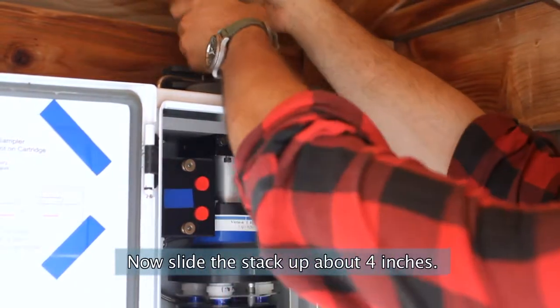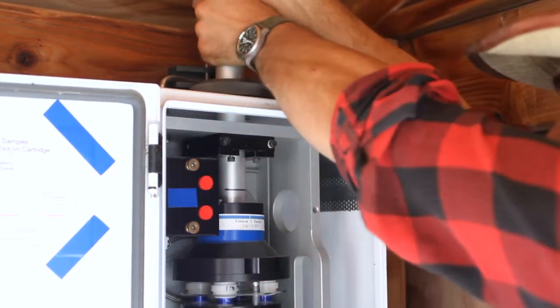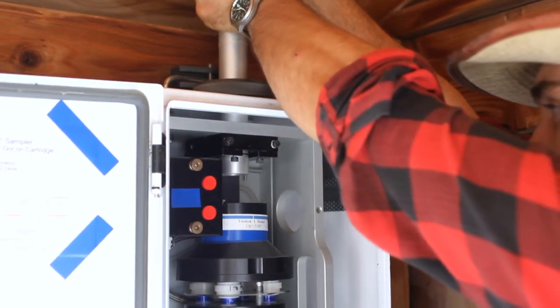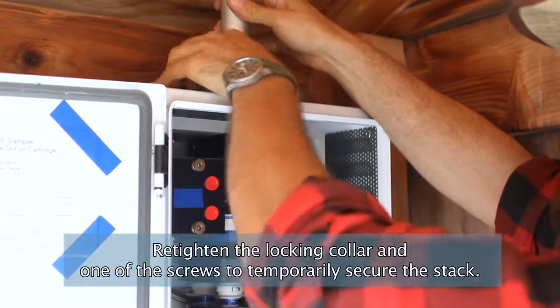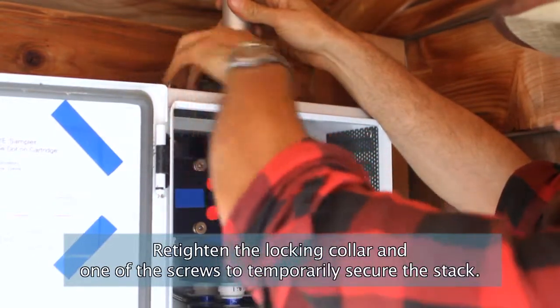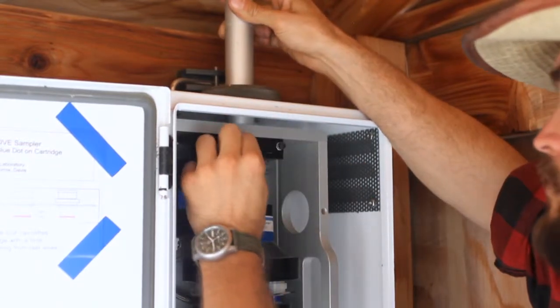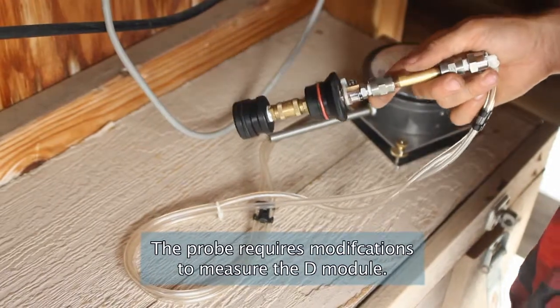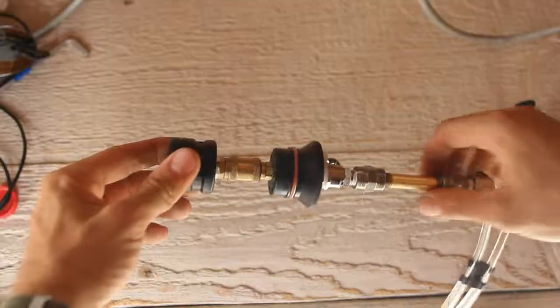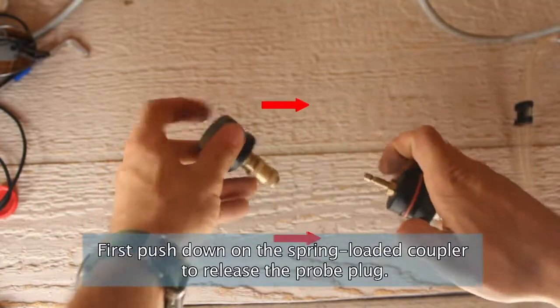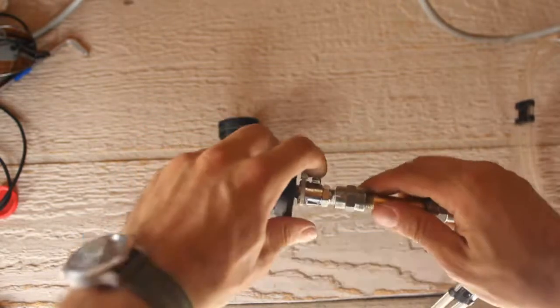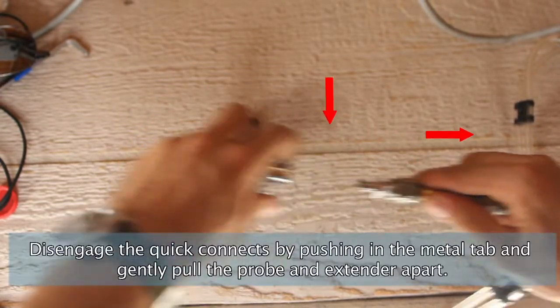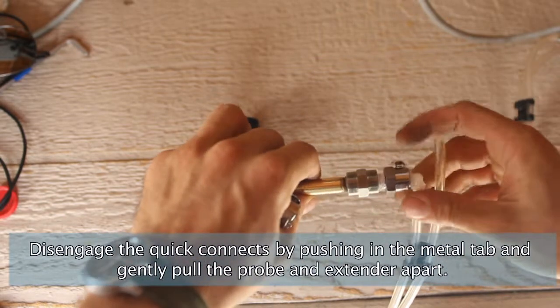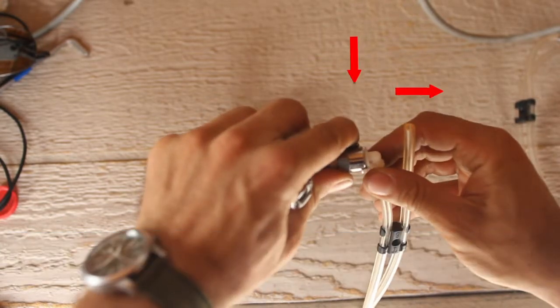Now slide the stack up about 4 inches. Retighten the locking collar and one of the screws to temporarily secure the stack. The probe requires modifications to measure the D module. First, push down on the spring-loaded coupler to release the probe plug. Disengage the quick connects by pushing in the metal tab and gently pull the probe and extender apart.